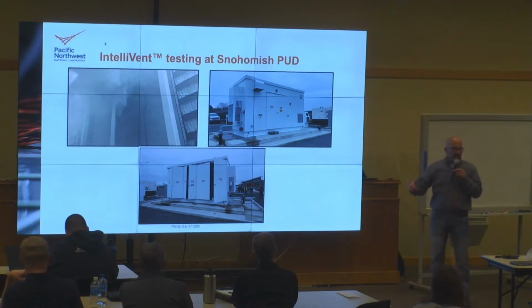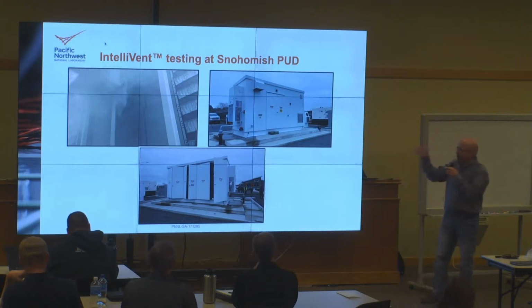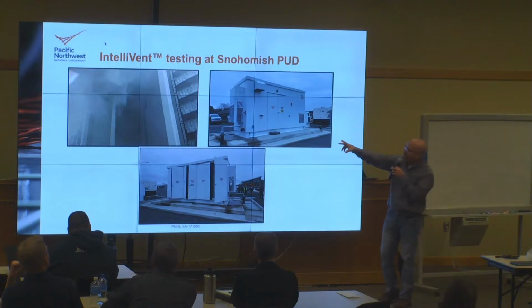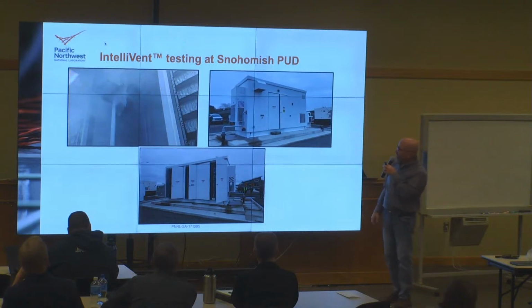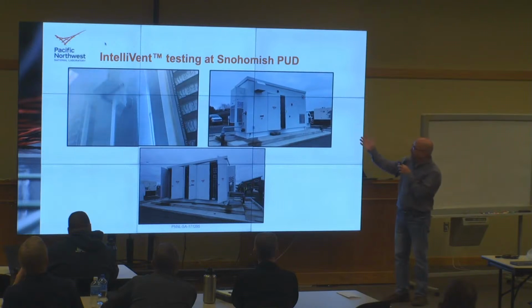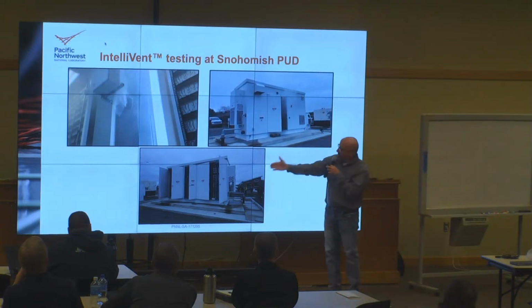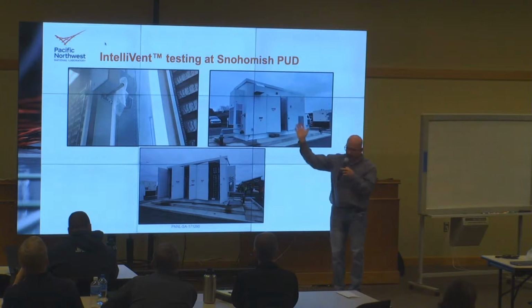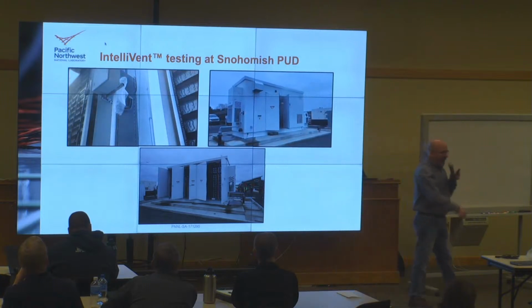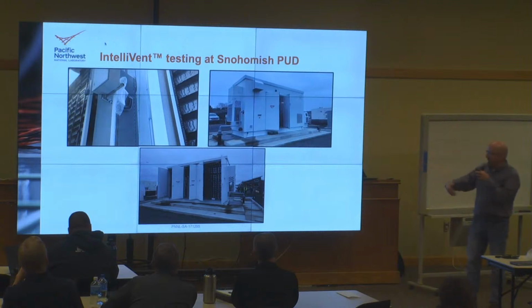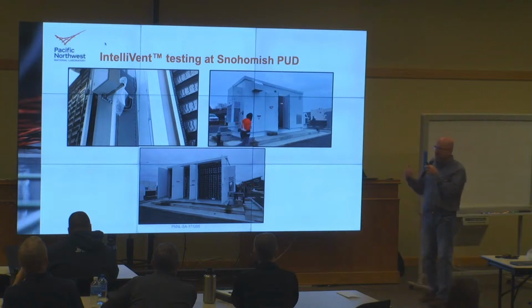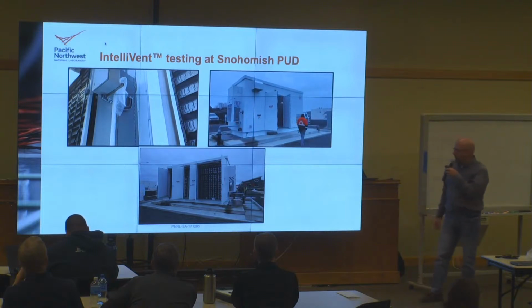Then when IntelliVent got introduced, they said, we're interested in that, and this was the first pilot project of it. This is a series of videos from inside. We put a smoke bomb, a fire alarm test bomb, inside there. You see the doors opening very slowly, and smoke is coming out. Because there are doors on both sides, it evacuates that space very quickly. They're still testing the dampening on the opener, so that's why it's inconsistent. But it doesn't have to open fast, just forcefully enough to ensure it opens.